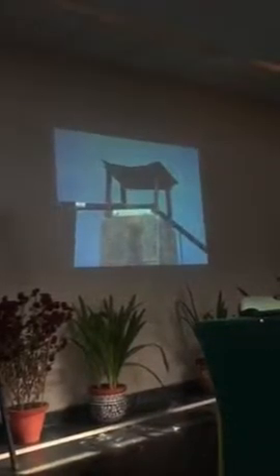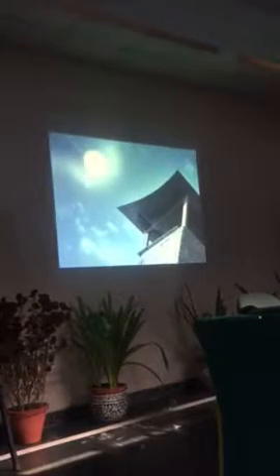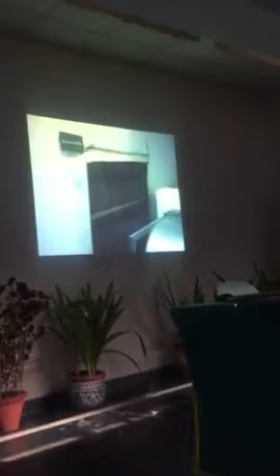There are sets of solar chimneys integrated with the rooms. These chimneys are dark-colored, lightweight structures and face southwards. They absorb heat by solar radiation, and the air inside it gets heated in turn and moves in an upward direction. As the hot air leaves the chimney, it creates a draft for the cool air from the tunnel to move into the room. During the monsoons, where the humidity level is high, an additional dehumidification system is installed to remove the moisture in the air.